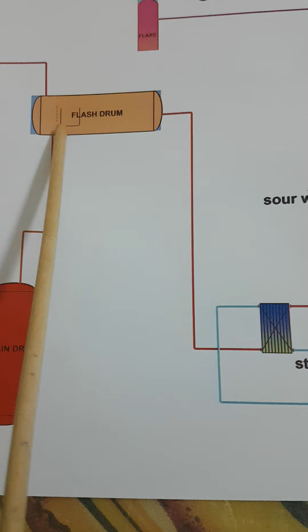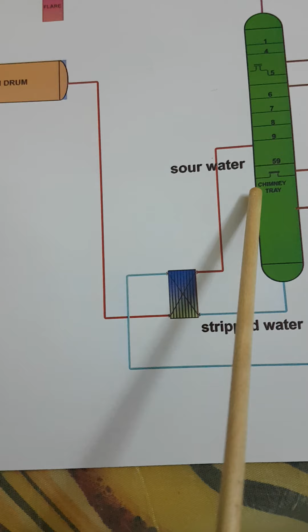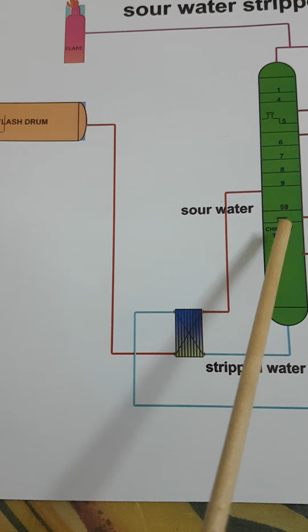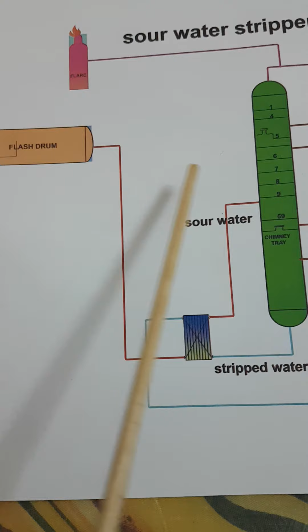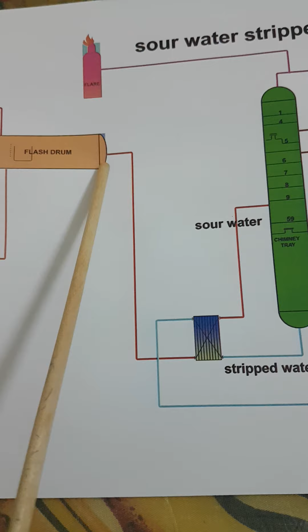And how do we maintain the level? Here we have a control valve, and this control valve is interlinked to this control valve. If the level of the stripper distillation column decreases, then the level control valve here will open. If the level decreases, this control valve will open, and if the level increases, this control valve will close. So this is how we maintain the level in the flash drum. This is a continuous process, so we need a control valve so that continuous operation takes place. Here we maintain only level and pressure.